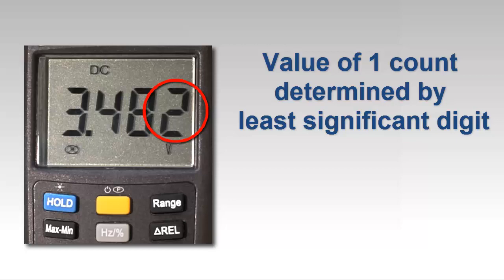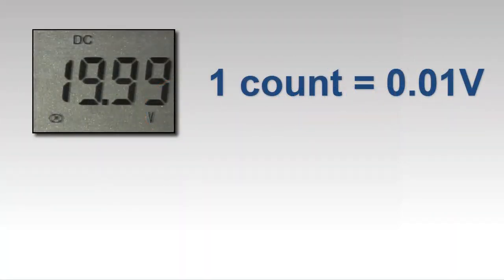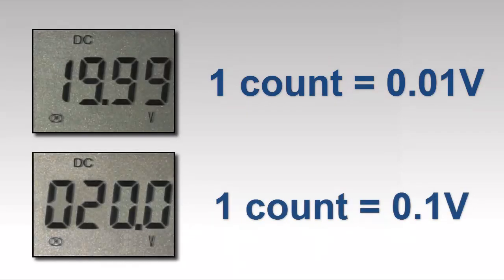In the preceding example, for a reading of 19.99 volts, each count equals one-hundredth of a volt. For a reading of 20 volts, each count equals one-tenth of a volt. Therefore, an instrument's measurement range can significantly impact accuracy, as we'll discover later in this video.